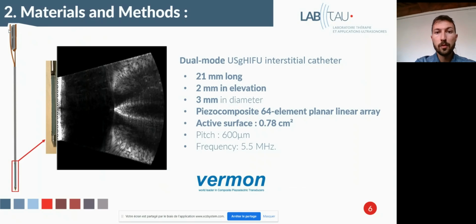For the materials and methods, I'm working currently with a second version of the probe, which is here, which is 3 times longer than the old one, because the probe is 3 millimeters in diameter and has 64 elements. It means 64 wires that we have to put in this 3 millimeters diameter. The frequency that we chose is 5.5 megahertz, and here is an image of what our probe can do. I forgot to mention that it's with the same probe that we do the therapy and the imaging part. It's a dual-mode catheter, so we can do imagery and therapy with the same probe.